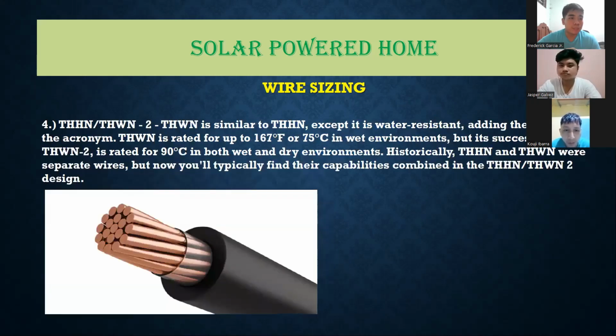Now, we also have THHN or THWN-2. THWN is similar to THHN, except it is water resistant, adding the W into the acronym, of course. THWN is rated for up to 167 degrees Fahrenheit or 75 degrees Celsius in wet environments, but its successor, THWN-2, is rated for 90 degrees Celsius in both wet and dry environments. Historically, THHN and THWN were separate wires, but now you'll typically find their capabilities combined in the THHN/THWN-2 design.